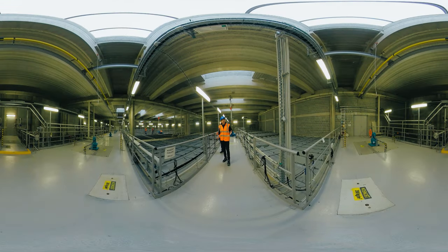Now here we are at the settling tanks. This is still the mechanical part of the process. As the flow of the water slows down in these tanks, even the smaller pollutant particles that got through the screens start settling to the bottom. To enhance this effect, the tanks are fitted with plates called lamellas that slant downwards, but you can't see them — they're underneath that murky water. Pollutant particles slide down the inclined surfaces of these lamellas to the bottom, where they're swept into a sump. This simple principle makes the process many times more efficient.